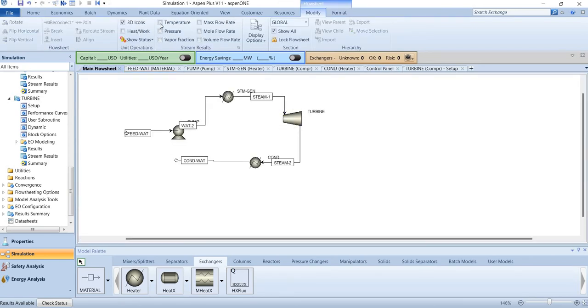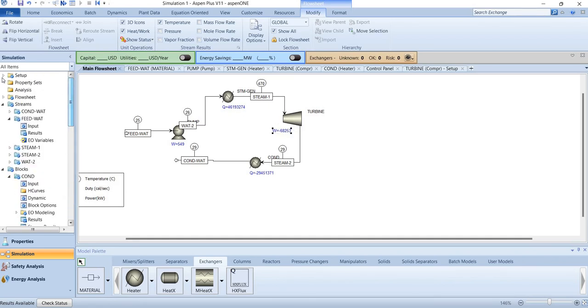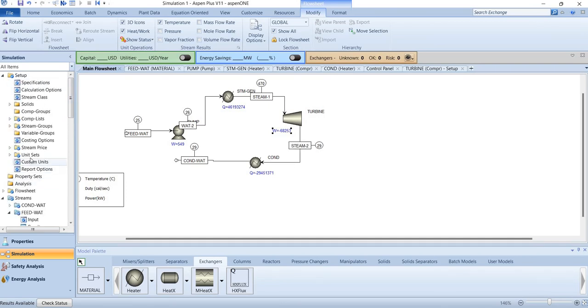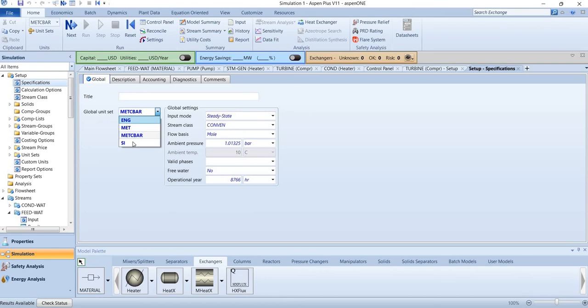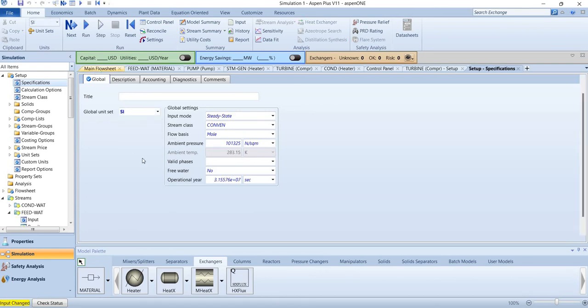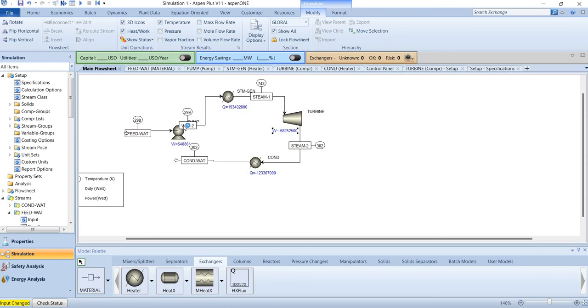And then you can see the temperature here, and you can see the heat and work. This is in kilowatt and this is in calories per second. You can change the units here - unit sets - and you can make it SI. And now duty will be in watts and the work is also in watts. It's 68 megawatts now, and you require at least 193 megawatts of heat to produce this amount of steam.